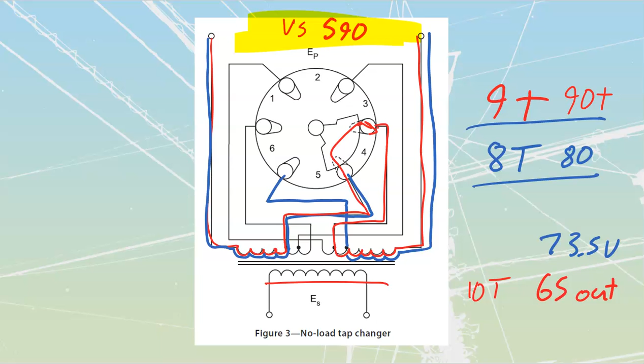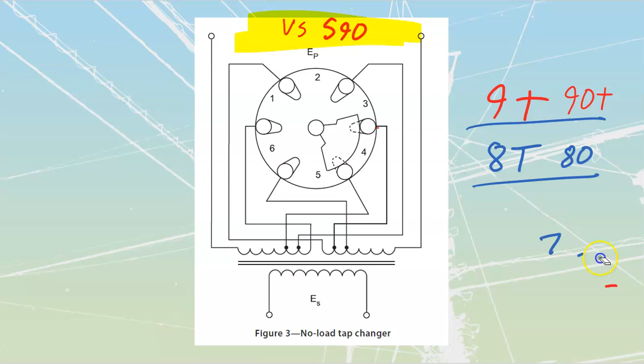These other ones, the no-load tap changers, are much more common inside of important industries, but where it's not critical - just an individual business. It might be a multi-million-dollar business, and they might have to do this once or twice a year. But most of these big businesses go through shutdowns, where they do a maintenance shutdown and a bunch of stuff happens. So as long as they time those shutdowns for the shoulder seasons, they're able to do the complete power off and change it over with no problems whatsoever.